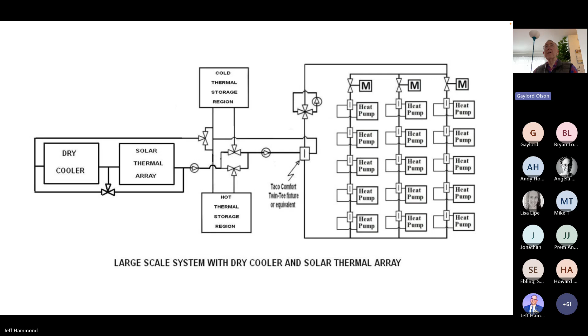That is a way to do what a pair of closely spaced tees will do, but it has two advantages over two closely spaced tees. You only need 4 pipe interconnections rather than 6, and you're also operating quite well whichever the direction of flow is. With 2 closely spaced tees, you have to pay close attention to the water flow direction in the primary loop. With the Taco Comfort device, it doesn't matter.